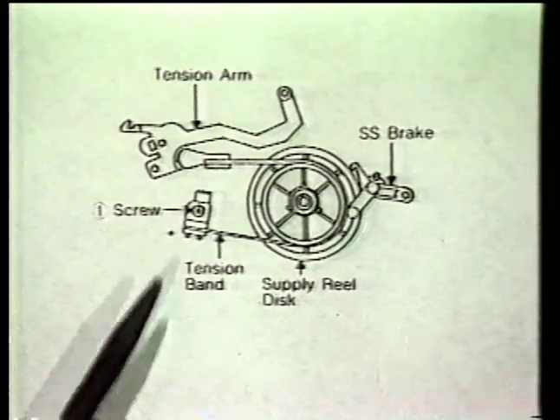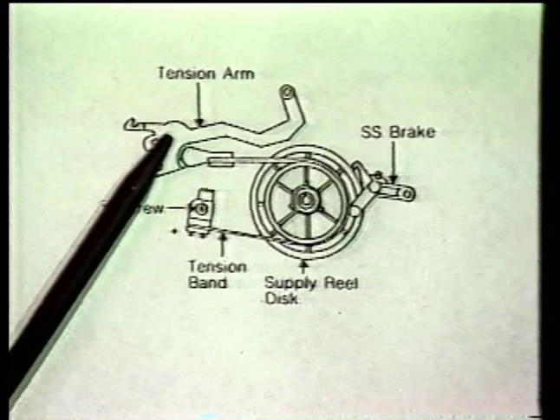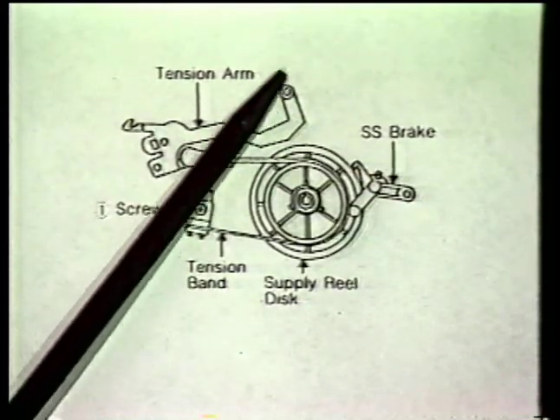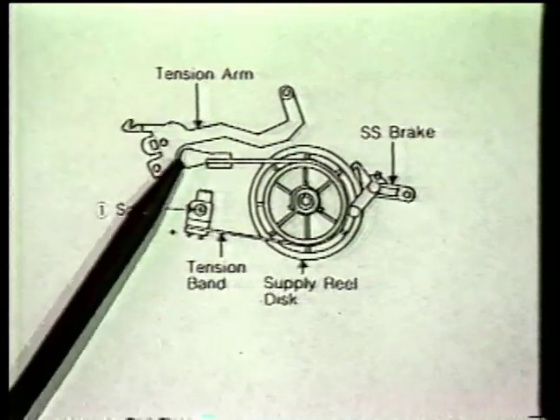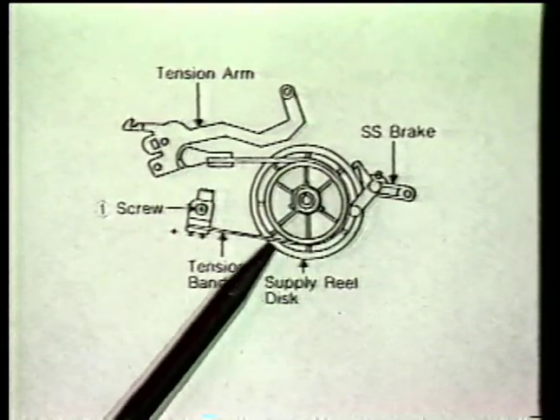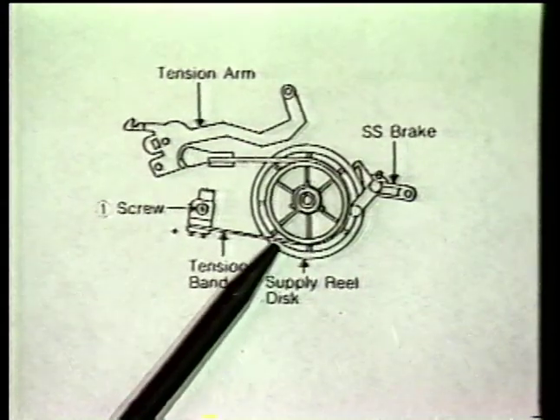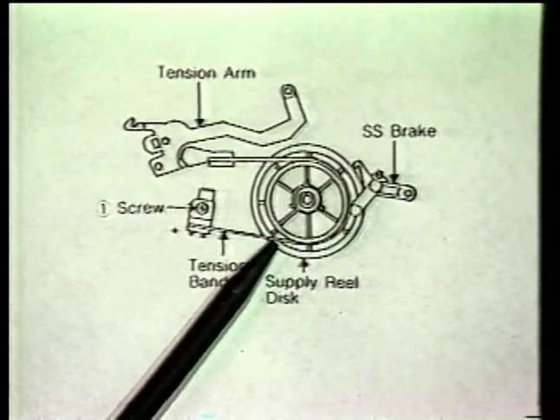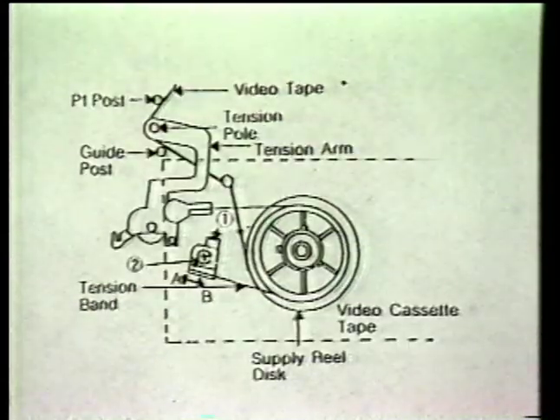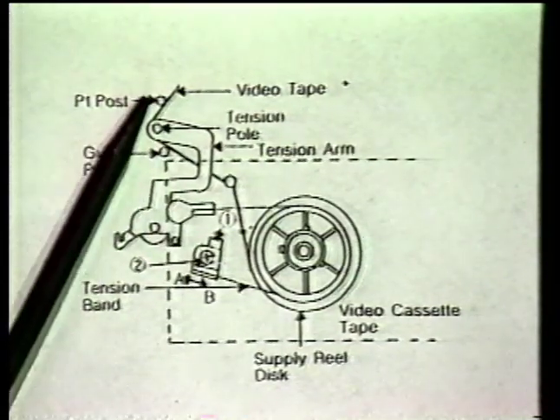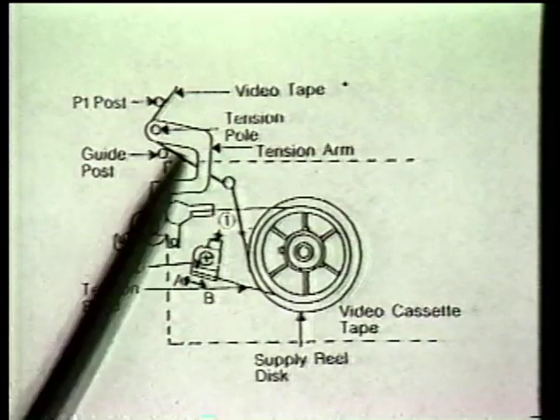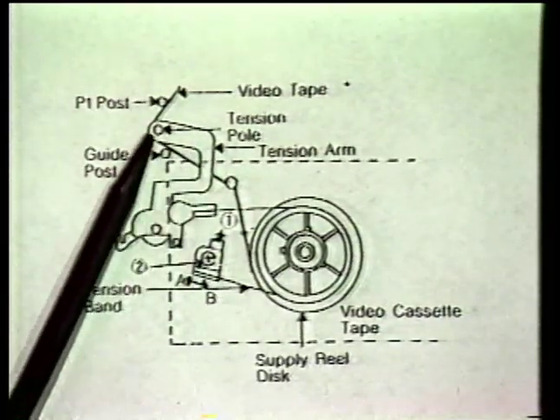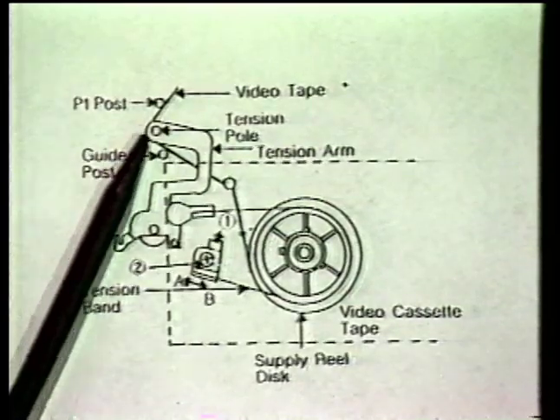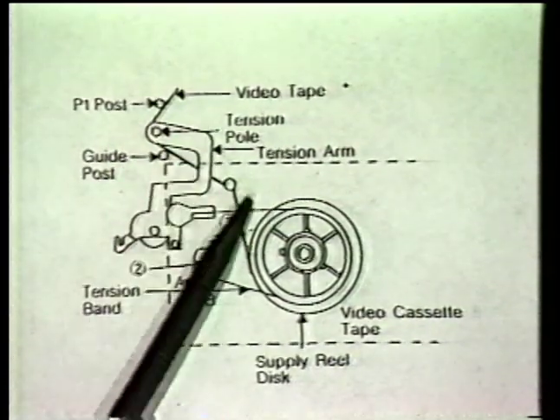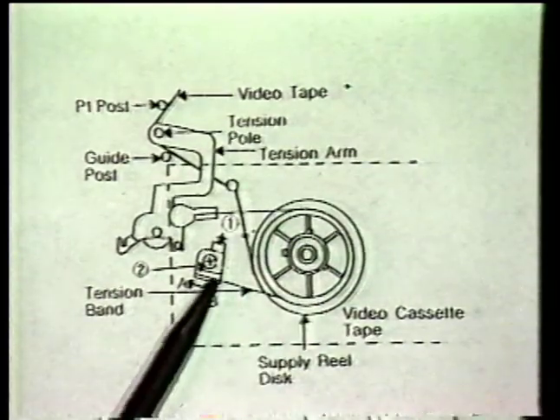Here's another configuration showing the rest position for this tension arm. As the cassette is inserted, the tension arm pulls out in contact with the tape, supplying the proper amount of torque by this little brake band that goes around the supply reel itself to provide the right amount of tape tension. Here's a slightly different but similar arrangement for the holdback tension arm. Notice the tape guides can be in different locations and different positions, but basically the arm from the supply reel does come out with a post out in the tape path, so that as the higher tension moves this arm back, it slacks this brake band that's around the supply reel.